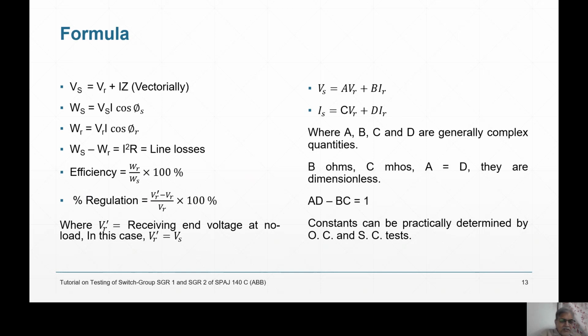Wr will always be less than Ws because some losses have gone - I square r losses have gone. For those I square r losses, nobody is paying. What is being paid is based on your meter rotating - you pay for what you are consuming. But what is consumed by the line, by I square R losses, by the iron loss and copper loss of the transformer, by the iron loss and copper loss of the generator - that is not paid by people. So you will have to bring these figures as low as possible.